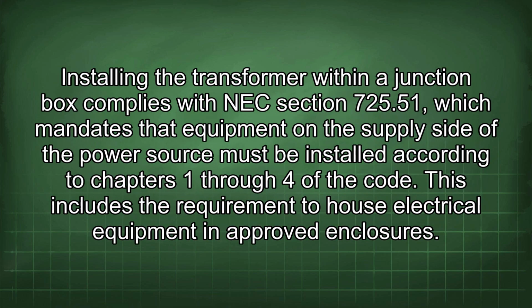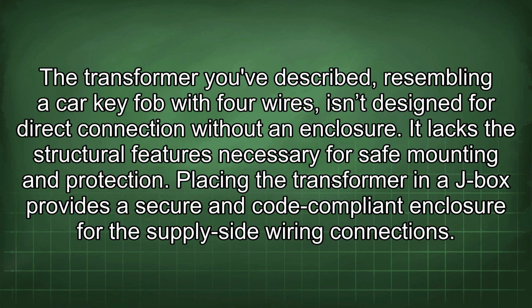Installing the transformer within a junction box complies with NEC Section 725.51, which mandates that equipment on the supply side of the power source must be installed according to Chapters 1 through 4 of the Code. This includes the requirement to house electrical equipment in approved enclosures. The transformer you've described, resembling a car key fob with 4 wires, isn't designed for direct connection without an enclosure. It lacks the structural features necessary for safe mounting and protection. Placing the transformer in a J-box provides a secure and code-compliant enclosure for the supply-side wiring connections.